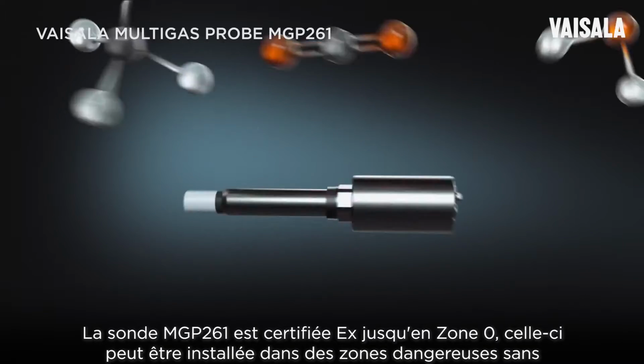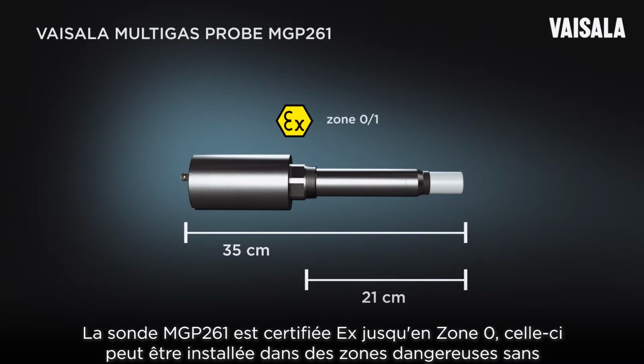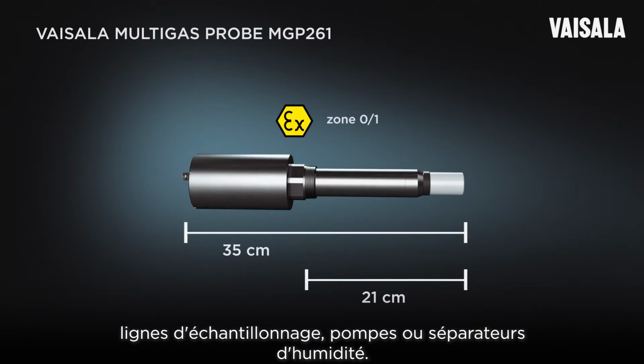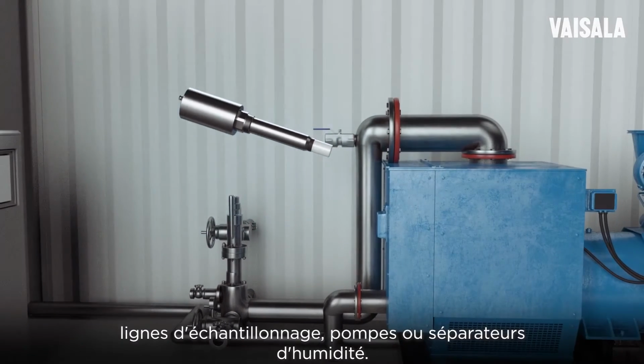The MGP-261 probe is EX certified up to Zone 0, and it can be installed in hazardous locations without any sampling lines, pumps, or moisture removal traps.